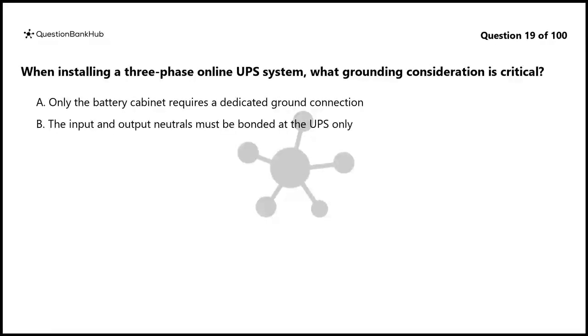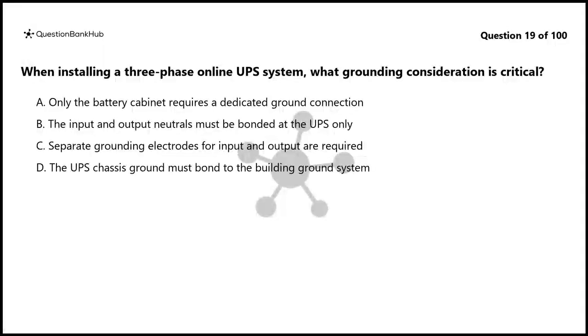Question 19. When installing a three-phase online UPS system, what grounding consideration is critical? A. Only the battery cabinet requires a dedicated ground connection. B. The input and output neutrals must be bonded at the UPS only. C. Separate grounding electrodes for input and output are required. D. The UPS chassis ground must bond to the building ground system.